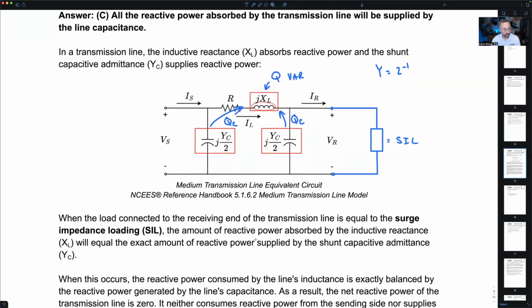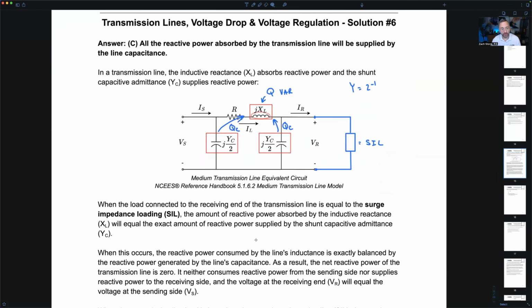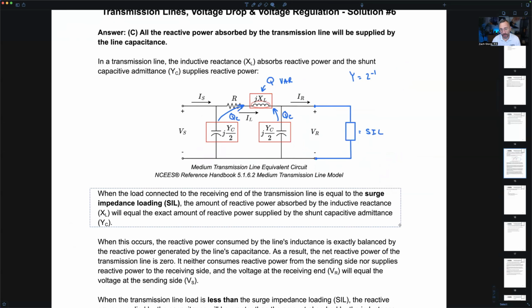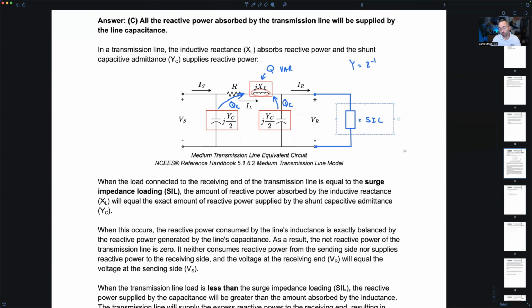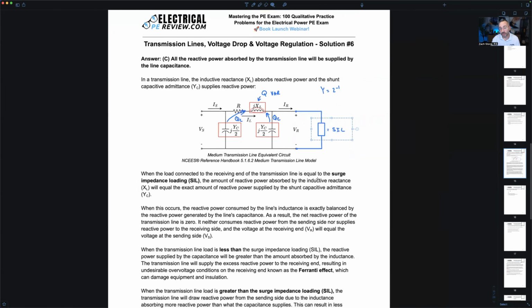All right, so looking at a few other good things to note in the solution, right? This pretty much just sums up what we talked about. When the transmission line is terminated in the surge impedance loading, it's going to be balanced in terms of its reactive power. It's supplying all of the reactive power it needs and no more. Very similar concept if you've been working through synchronous machines. It's a very similar concept as a unity power synchronous machine that has ideal excitation. It's neither exporting VARs or importing VARs. It's got a net reactive power of 0, right? It's providing its own reactive power, no more, no less. All right, so when our load is equal to the surge impedance loading, we've got net 0 reactive power.